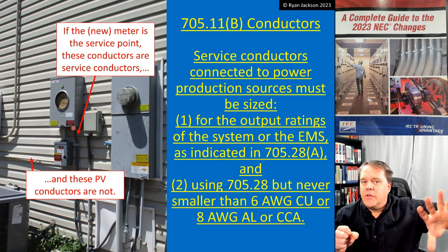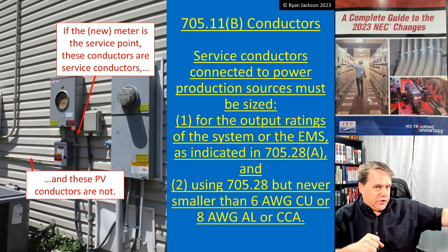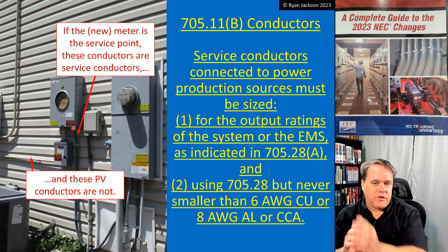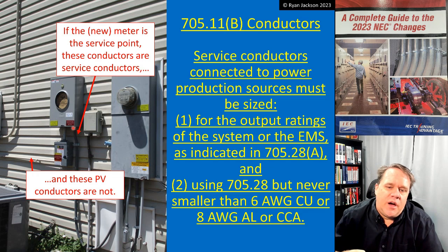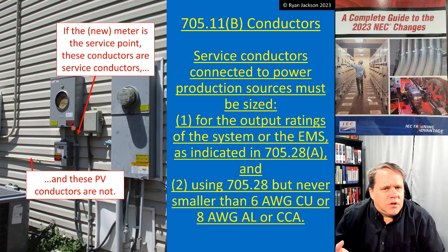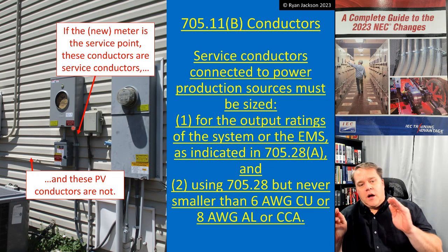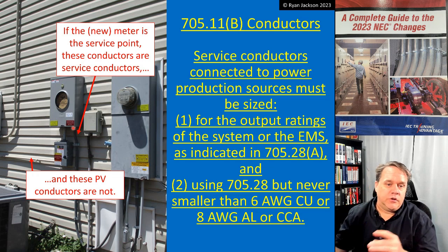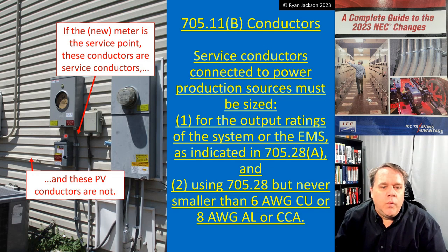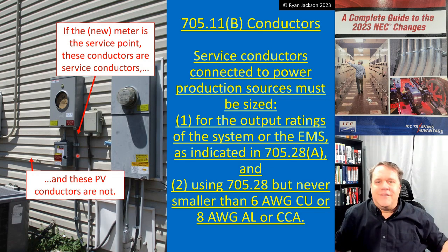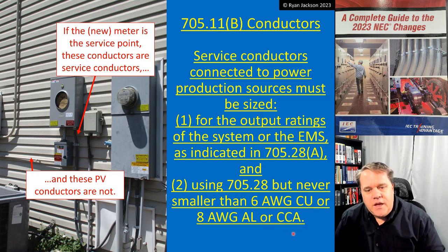Maybe you install an energy management system on the PV system and say you're never going to generate more than 30 amps. You'd take 30 amps times 125% because we treat it as a continuous load, and you'd size those conductors based on the energy management system settings. And number two: not smaller than 6 AWG copper or — I initially said 8 AWG aluminum, but let me check the code. We need to have a minimum size because if the utility conductors fault, we don't want small wires to just evaporate.